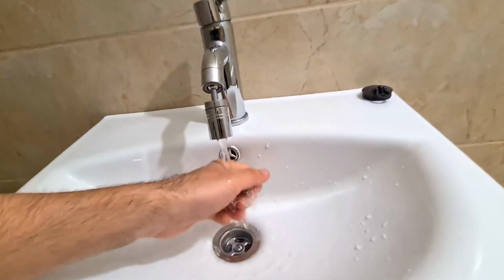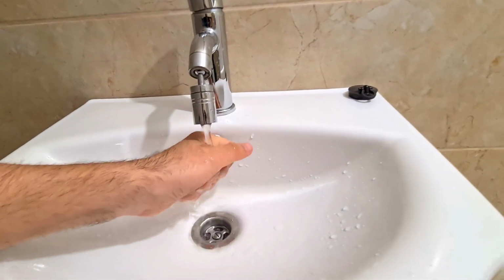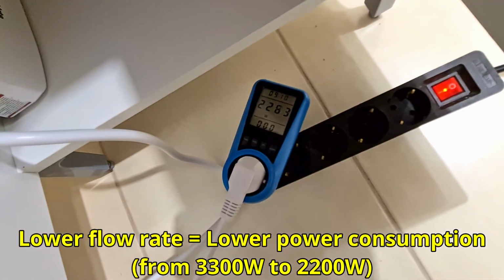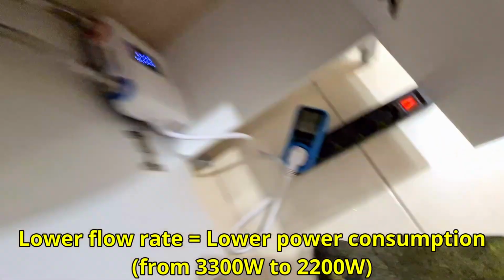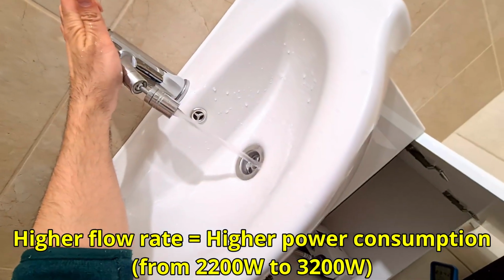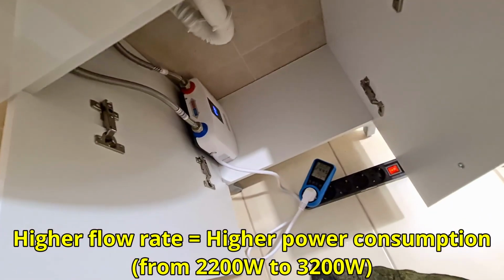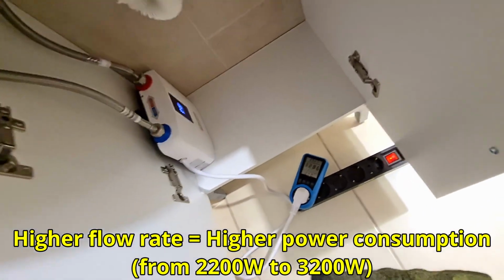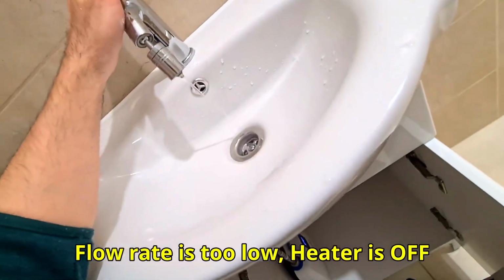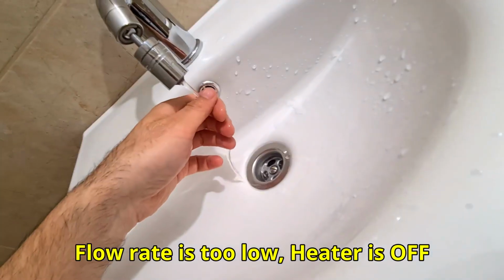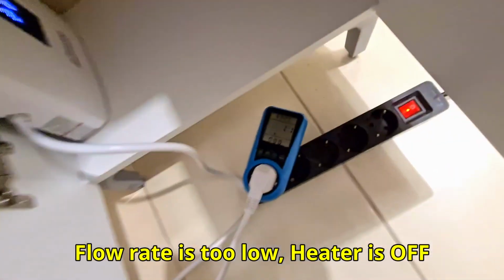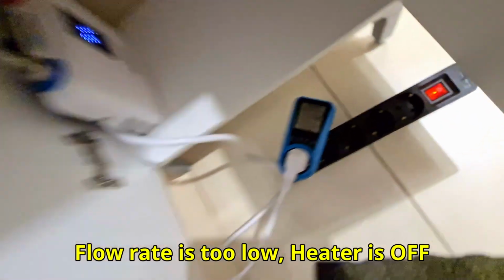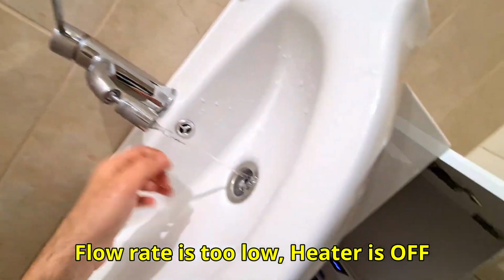It's warm to the touch, so you can definitely use it for cleaning. And it's consuming 2200. So if I increase the flow rate, 3000, it's consuming more. Reduce the flow rate, that's a little bit too small. Yes, 1 watt. So you need a little bit of flow.